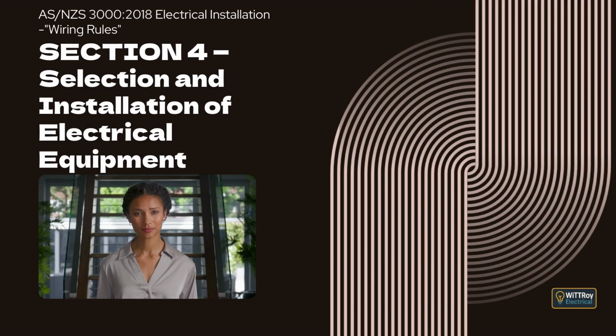This clause explains that where socket outlets of the same type are installed within an installation, their connection order must be consistent. It also explains that for 3-pin flat-pin socket outlets, the arrangement of earth, active, and neutral must follow the specified clockwise order when viewed from the front of the socket outlet, ensuring correct polarity throughout the installation.